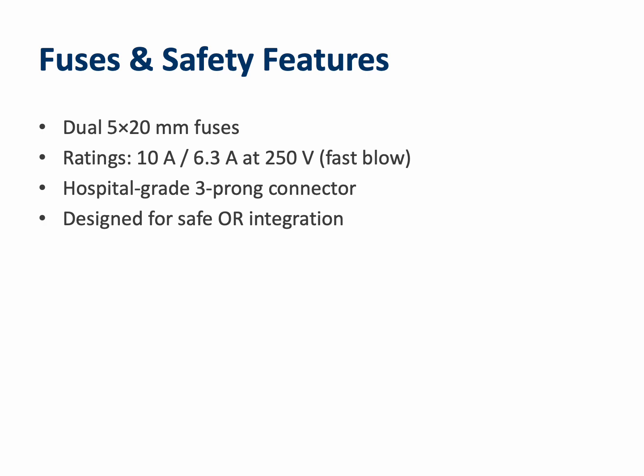For safety, the FT10 is equipped with dual 5 by 20 millimeter fuses, rated at 10 amps and 6.3 amps at 250 volts. Fast blow type. These fuses act as a critical protection against electrical overloads. The unit also connects via a hospital-grade 3-prong plug, which ensures grounding and minimizes shock risk. Together, these features ensure that the FT10 integrates seamlessly with the hospital's electrical safety infrastructure, reducing risk for both patient and operators.